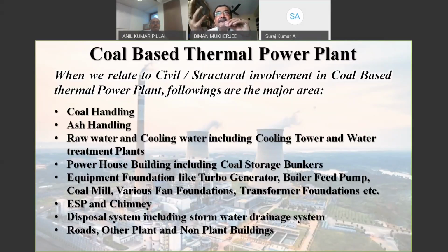Now, on the other side of the boiler, the boiler is designed sometimes as corner fire, sometimes front fire, sometimes all side fire. So there are a lot of designs. We don't go into that. Basically, water is in the boiler tubes, which hang from the top of the structure, which has a boiler drum there, and from there all these pipes are hanging, and those pipes make the boiler wall. Basically, the boiler is a structure which is actually hung from above, directly hanging with some eye rods and all.